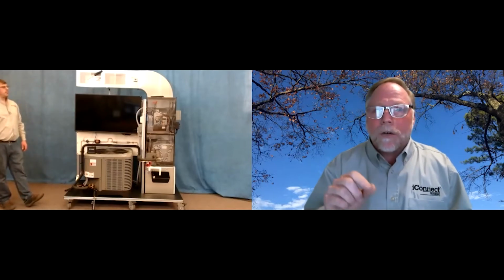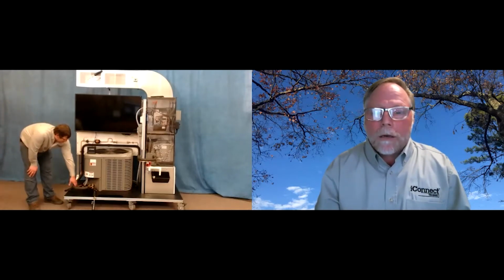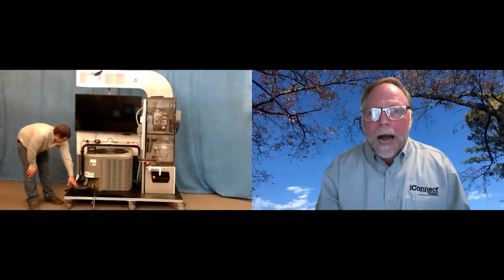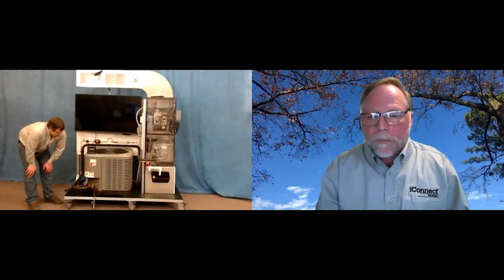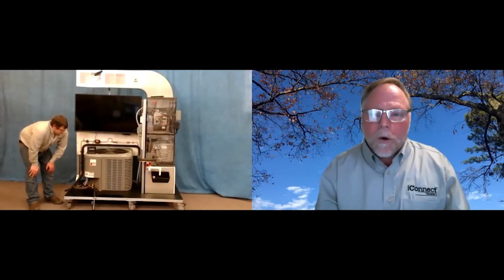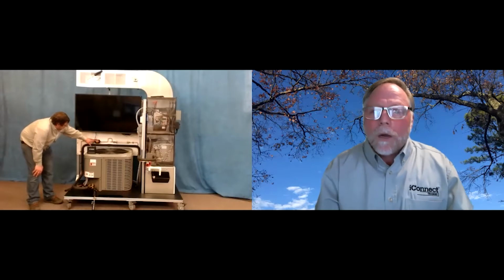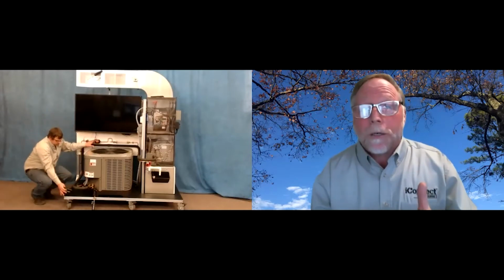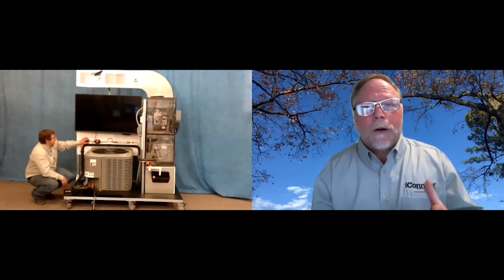Now, one of the things that I like to do as a lesson is as you go back through, you talk about the condition of the refrigerant in each of those lines. So Nick, we go back down to that liquid line service valve down there. And okay, as we go through it, we'll describe that it is a high pressure subcooled liquid leaving the condenser. And as it goes up, Nick, you go up to the filter dryer there. Then you talk about the filter dryer, how not only does that filter refrigerant, but it dries it out a little bit. One thing I like about HVAC components is they are named for what they do. So if you want to know what they do, just look at the name of it. So a condenser condenses refrigerant. A filter dryer filters out debris and dries out some moisture.